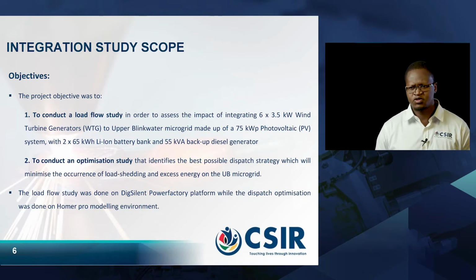The second objective was to conduct an optimization study that identifies the best possible dispatch strategy, which will minimize the occurrence of load shedding and excess energy on the microgrid. The load flow study was done on the DIgSILENT Power Factory platform, while the dispatch optimization was done in the HOMER Pro modeling environment.